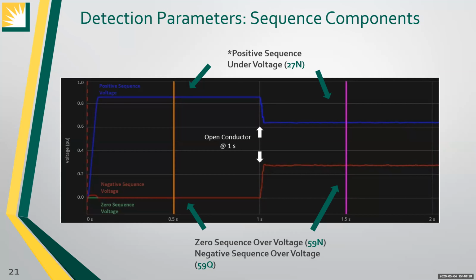At the 1 second mark, when the open conductor has occurred, we can see an almost immediate change in the magnitude of all three sequence components, where the 0 and negative sequence voltage magnitudes increase significantly and the positive sequence voltage magnitude decreases significantly as well. This behavior was observed consistently throughout our simulations, and thus we decided to use them as part of the detection parameters: positive sequence under voltage 27N, zero sequence over voltage 59N, and negative sequence over voltage 59Q. Next slide, please.